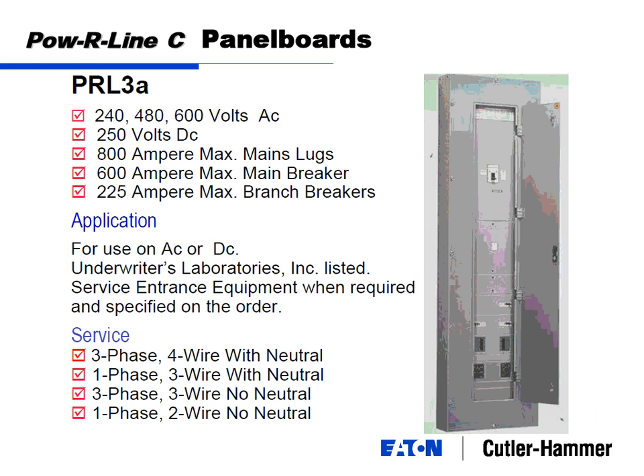Pow-R-Line 3 panel boards. This is kind of the hybrid. I talked about Pow-R-Line 1 and 2s being lighting and receptacle panels. Pow-R-Line 3s are kind of a hybrid between lighting and receptacle and a power distribution panel. The voltage rating jumps up to 600 volts, which ain't really going to be used, but it gives you a lot more flexibility on the voltages you want to use, or DC even. And it goes up to 800 amps for main lugs or 600 amps for a main breaker.